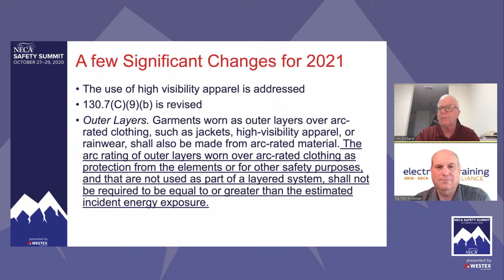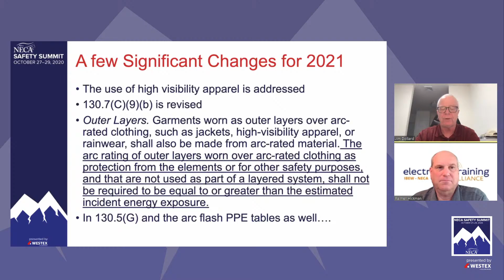Okay, all right, this change, and you see it in 130.7, that's the general requirement for outer layers, but we refer to it in table 130.5G, which is a table for PPE if you're doing the incident energy analysis. And we also refer to it in the arc flash PPE tables as well. And Palmer, there's a new table. The committee pushed back for multiple cycles. They didn't want to add a table that got us into maximum use voltages, et cetera, for gloves. Can you discuss how the committee came to accepting this table and why it looks like it does?